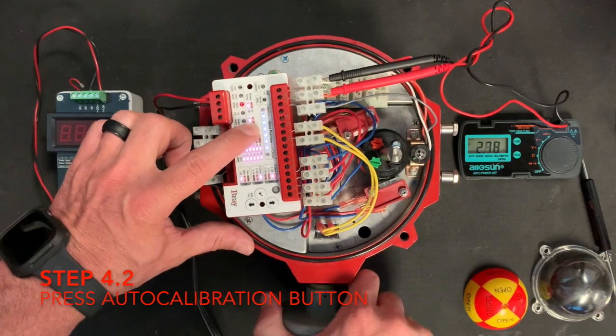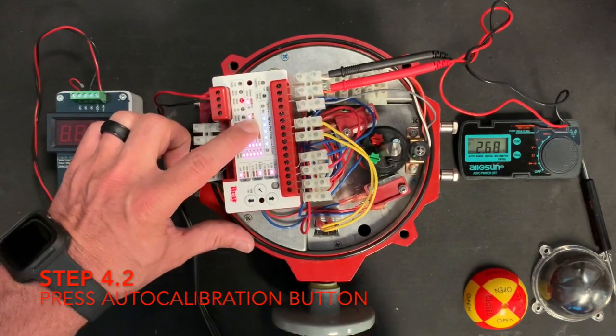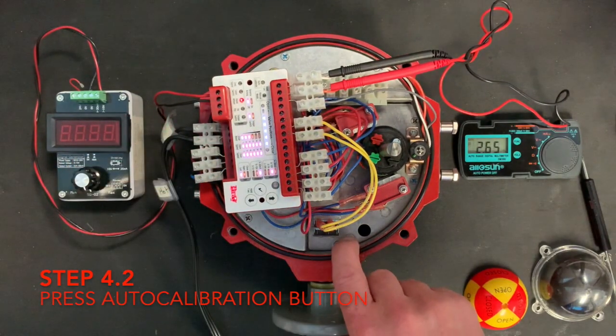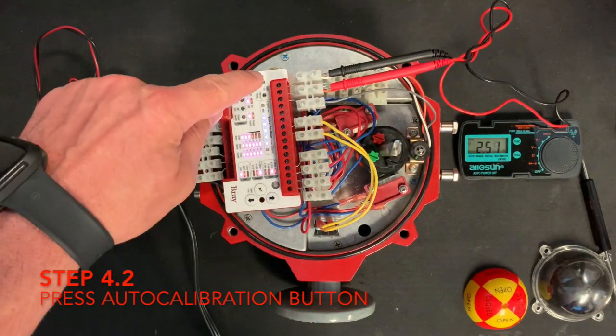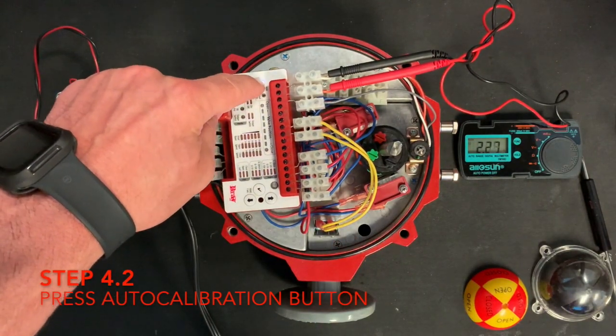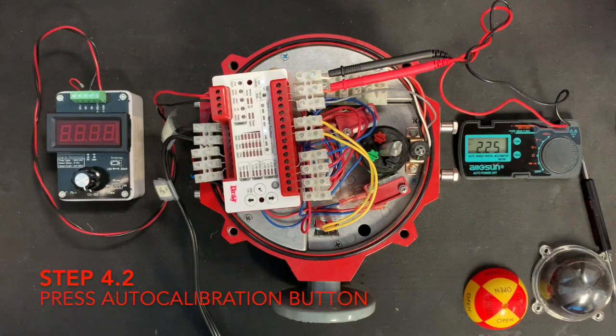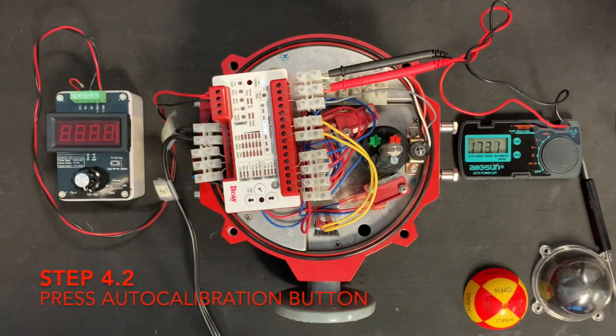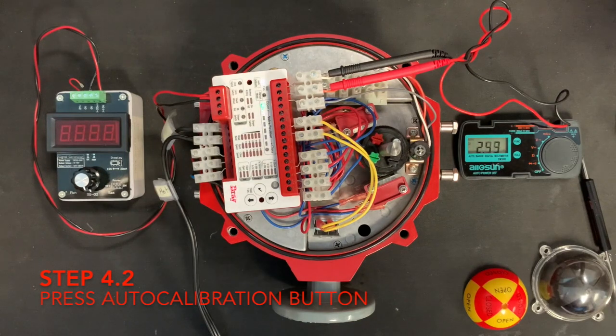For NXT servo actuators, put the servo NXT into auto calibration mode by pressing the auto calibration button. Wait approximately 2.5 to 7.5 minutes for the auto calibration to complete before moving to the next step.